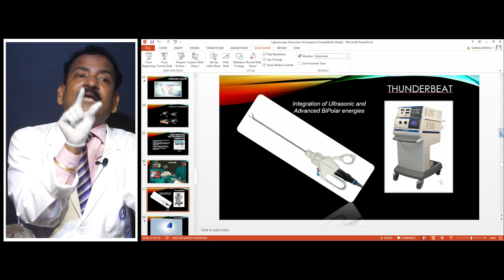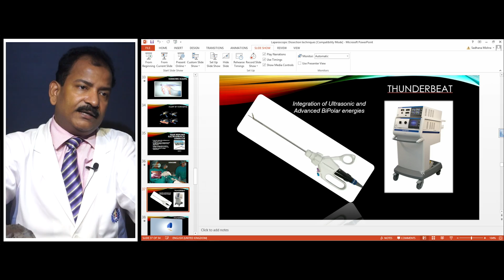Purpose of the jaw is that if you have to seal it, then it will help you to bring the tissue near the vibrating jaw. So, that pressure will melt the elastin and it will seal by pressure effect. So, holding is only required for vessel sealing, otherwise you do not have to close it. Never keep the jaw closed if tissue is not in between, otherwise it will cut the silicone and your instrument will get spoiled.